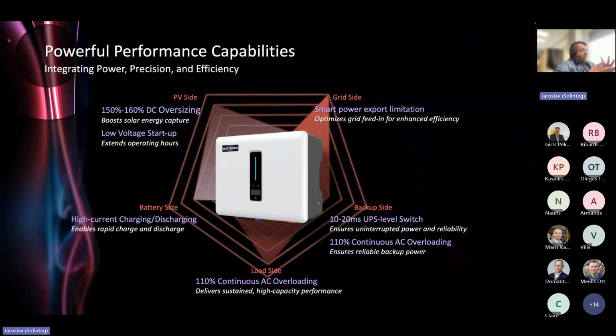Now about our inverter's powerful performance capabilities. You can oversize the PV size to 150 to 160%. That means the energy will not be lost, because you can use all the energy from the PV modules. Even with this 10 kilowatt inverter, if you oversize it to 15 kilowatts, the inverter can still feed 10 kilowatts to the grid and 5 kilowatts to the battery. On the battery side, we have high current charging and discharging possibility. That means we can very quickly charge the battery and use the electricity that is stored in the battery.